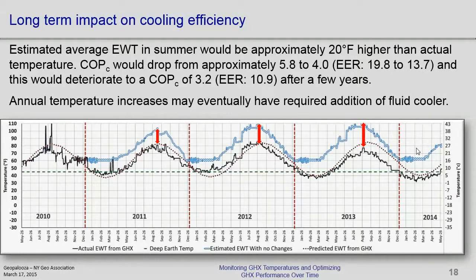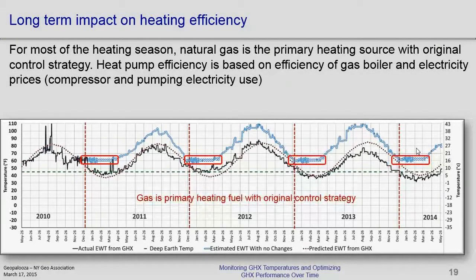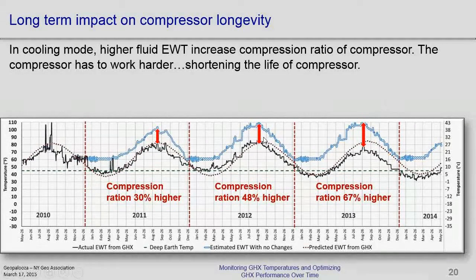So this kind of flattens out. Here, during the winter, the gas becomes the primary heat source. If we allow it to continue like that, this is going to heat fine. It's going to be a lot more expensive to operate, but it's going to heat fine. But compression ratio gets higher and higher. It's going to shorten the life of the compressors. And compressors are going to start failing in the second or third year probably.